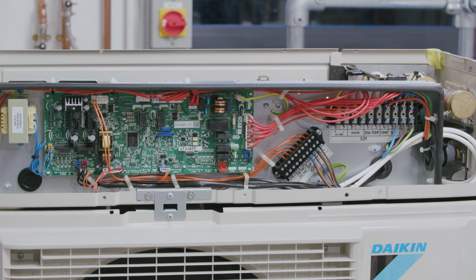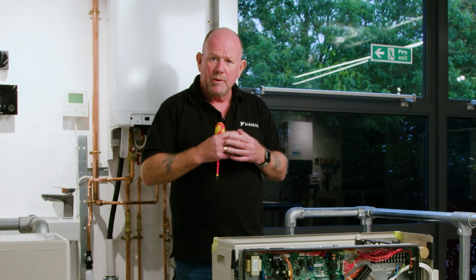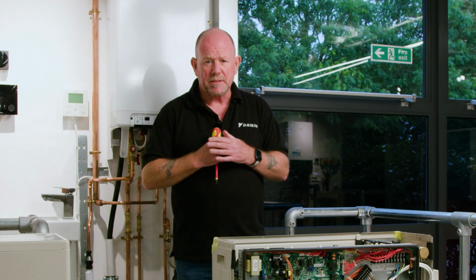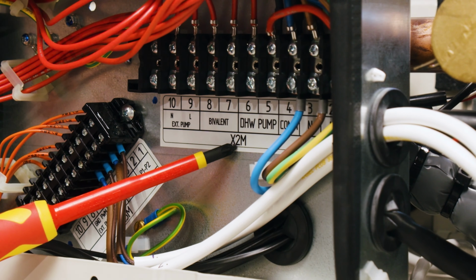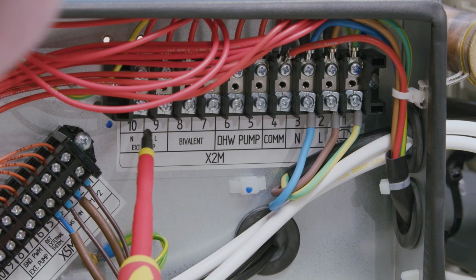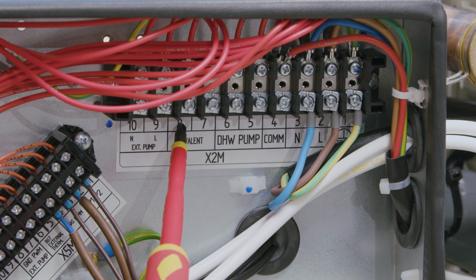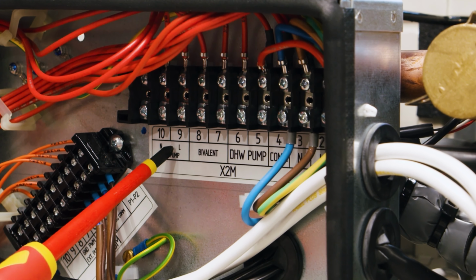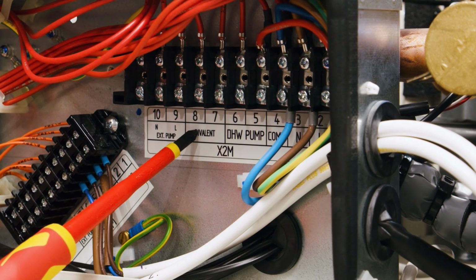A concern for most installers is the wiring of the system. The good news is the system is probably easier to wire than your existing gas boilers. In the world of Daikin, our terminals are clearly identified, normally with the letter X, a number, and then the letter M. The numbers are unique, so there's no problem finding the correct terminal strip. The demountable connections are all numbered, as you would expect, and beneath the numbering, there's a description of the item that connects into that particular terminal. Controls wiring is straightforward. If you come on the training course, you'll go away with schematics to help you with this.